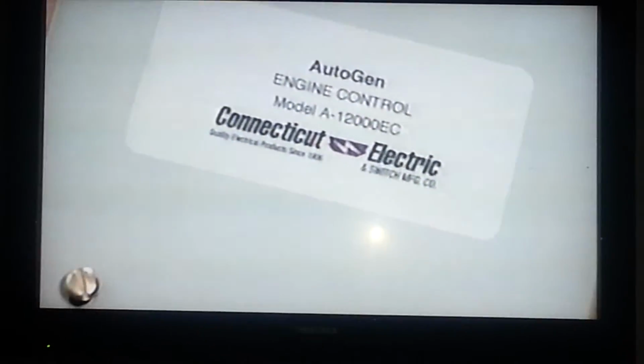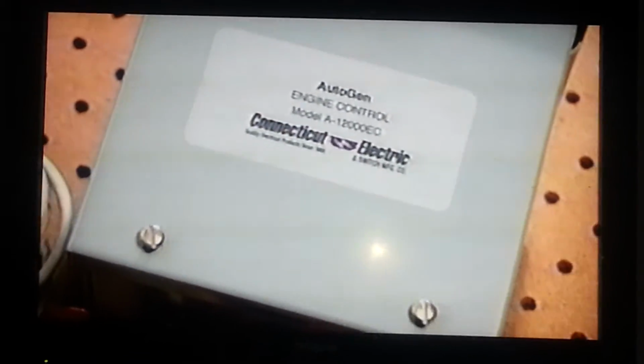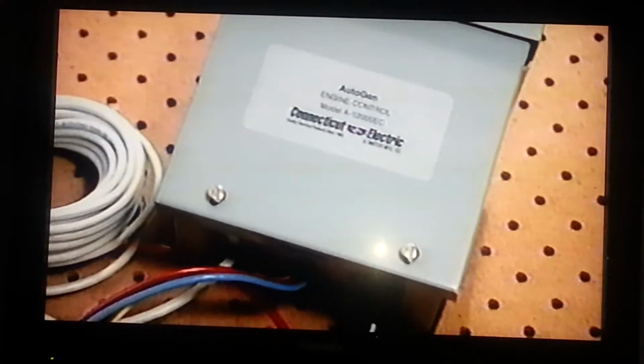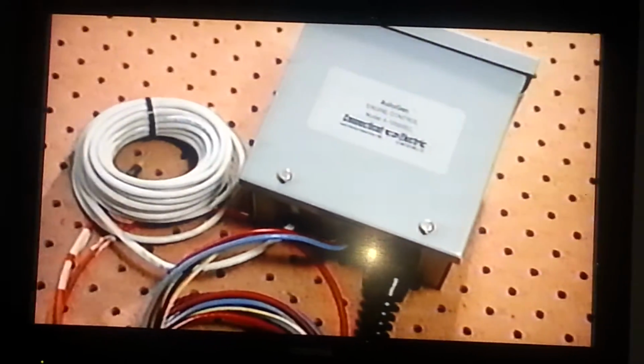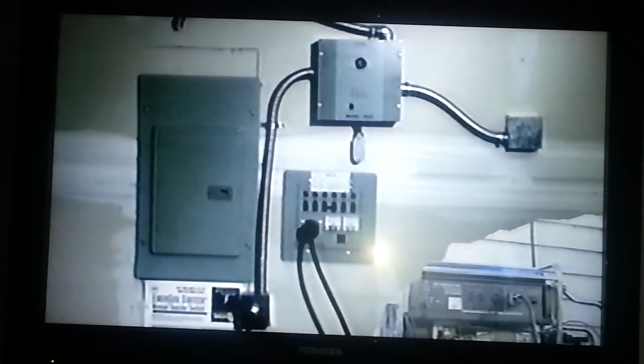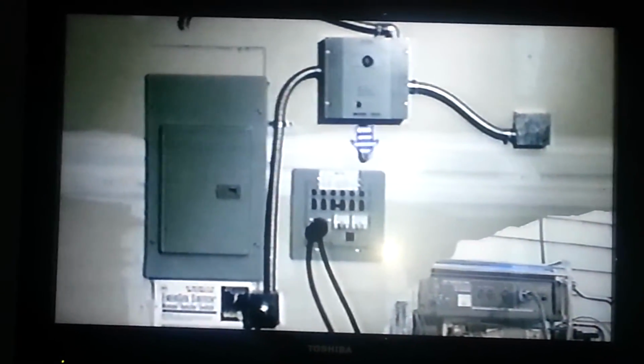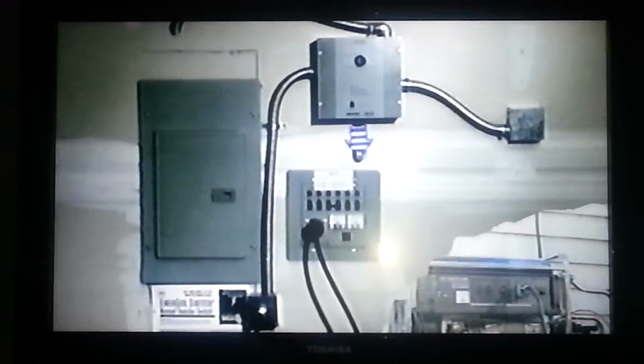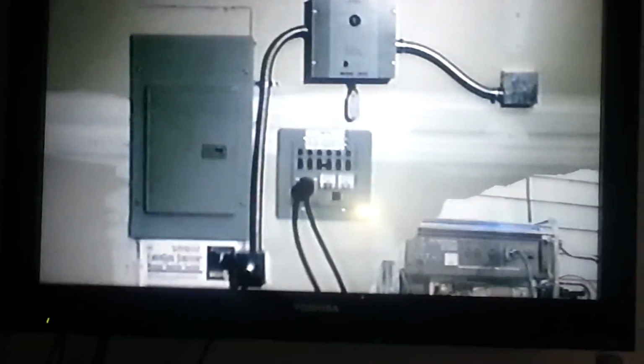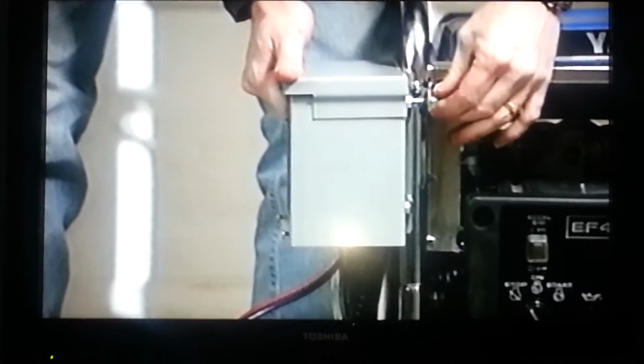Now you are ready to install the second component of the ATS, the engine control. The engine control automatically starts and stops your generator on a signal from the ATS transfer switch. The engine control also monitors and charges the generator battery. Begin by disconnecting the battery cables at the generator battery. Then mount the engine control on the tubular frame of the generator using the strap and two nuts located on back of the engine control.